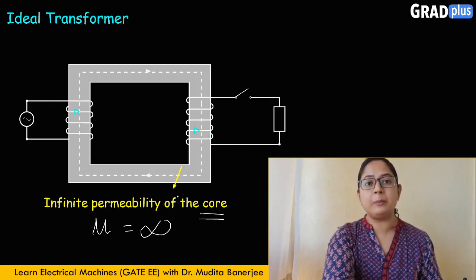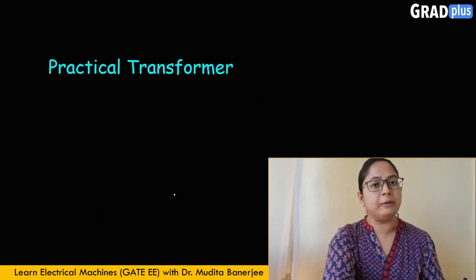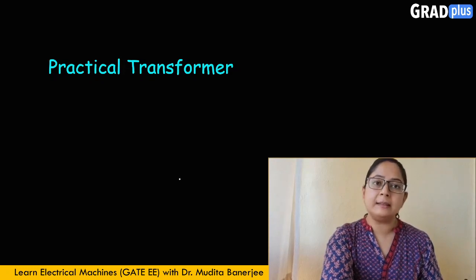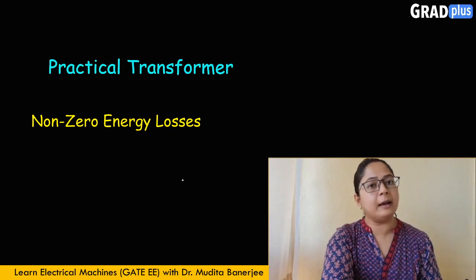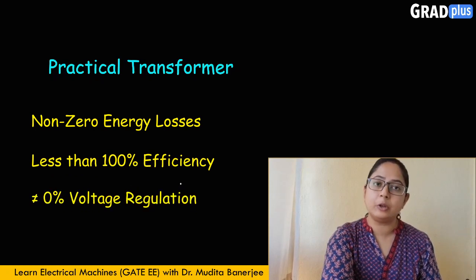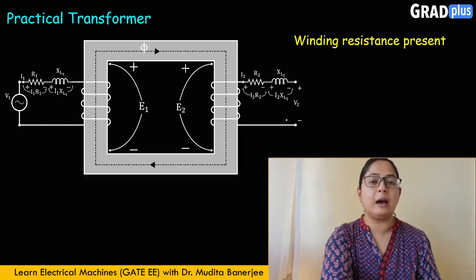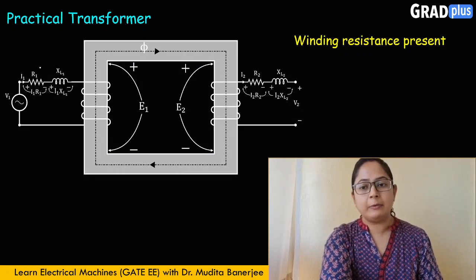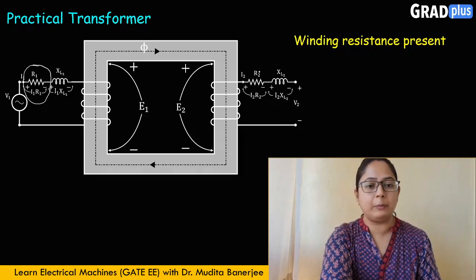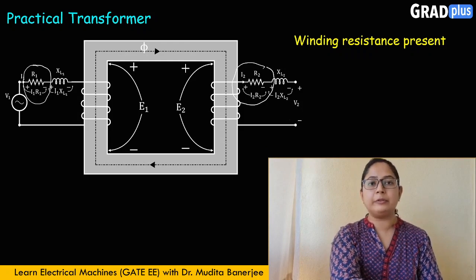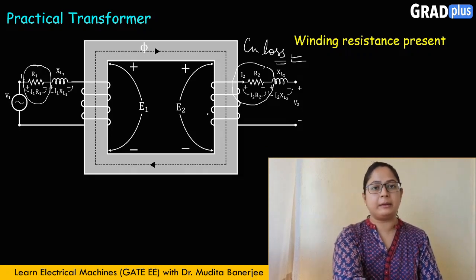All these characteristics are present in the practical transformer. A practical transformer is a real-time transformer which has energy losses in it. The core has finite permeability, its efficiency is not equal to 100%, and the voltage regulation is not equal to 0%. The first point is it has winding resistance — winding resistances R1 and R2 are present in a practical transformer, as seen in the diagram. The presence of winding resistance means copper losses are also present, which decreases the efficiency of the transformer.